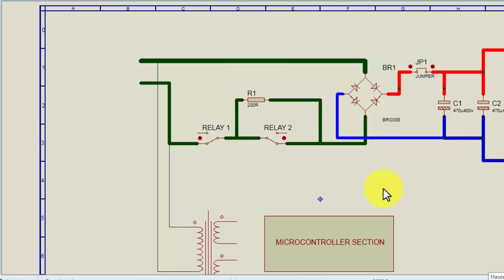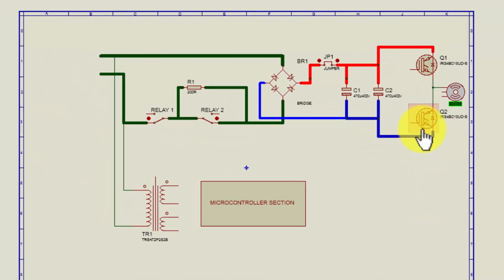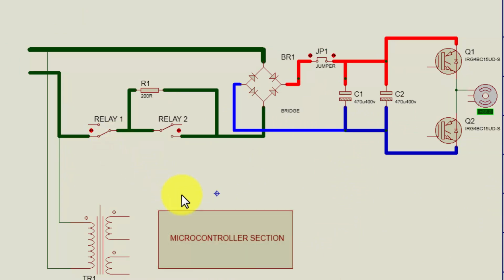In our fault condition, the resistor was heating up during the initial startup. Why? Because these IGBTs were damaged. Both were short circuit, so the DC rail was directly connected from positive to negative. After a specific time, the microcontroller was turning on this relay number 2, because this soft start section is controlled by the microcontroller.